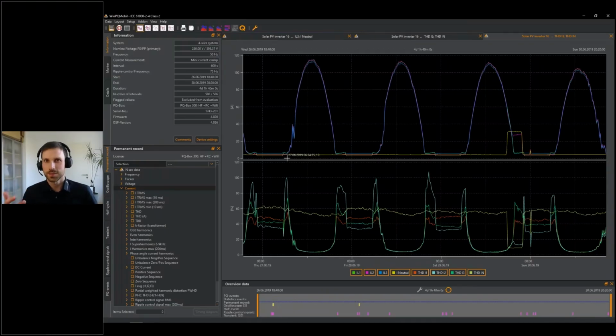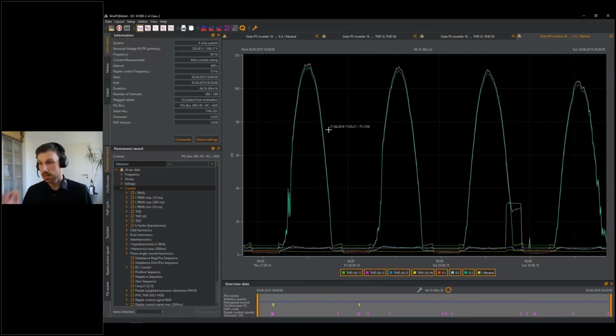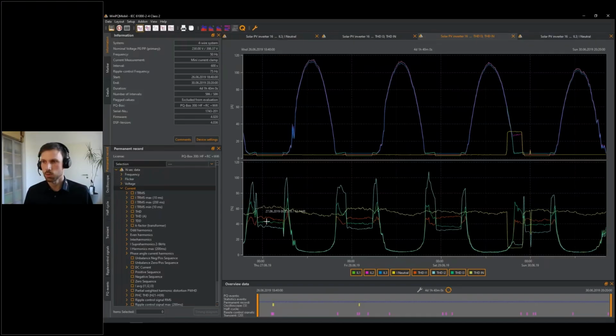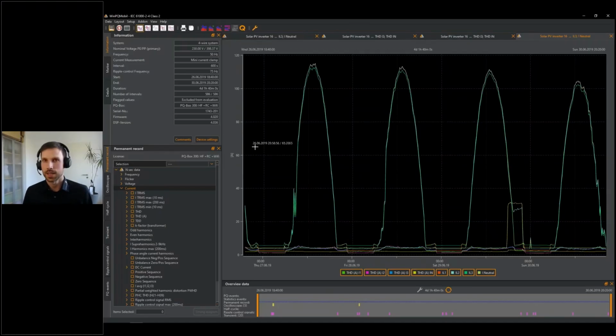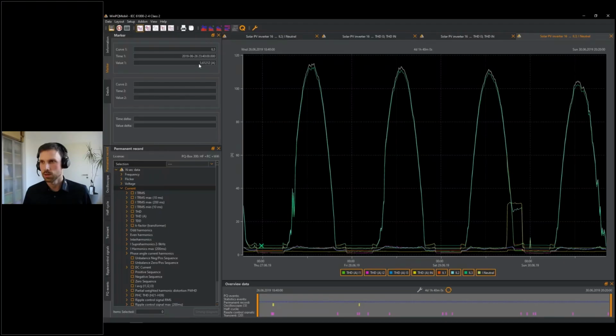And now, last but not least, to see how high the actual harmonic current was, I can also go for the THD in amps. So this is very useful. I open this and now I see, okay, what previously was seen as around 100% and very high levels at night, in percent of the nominal current, is actually not that bad, because in amps we got around 5 amps, and during the day we got around 114 amps. But the THD during the day is not as bad.